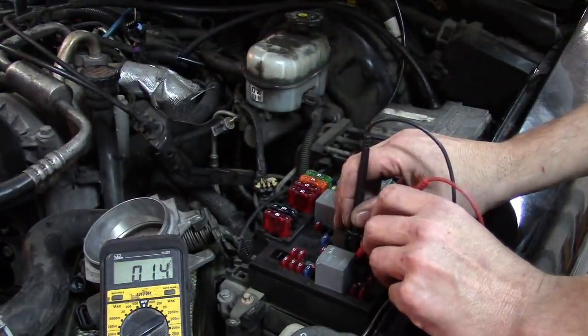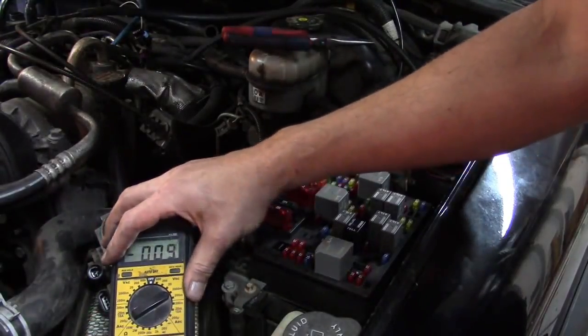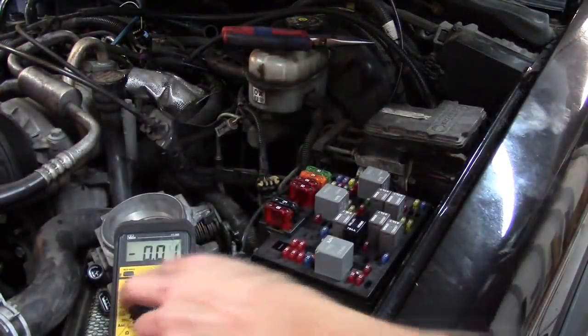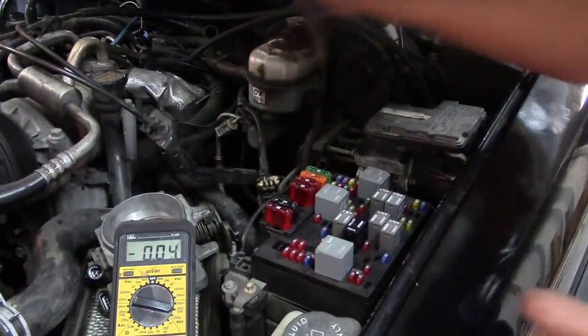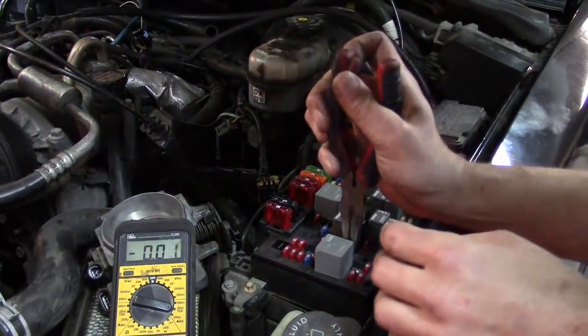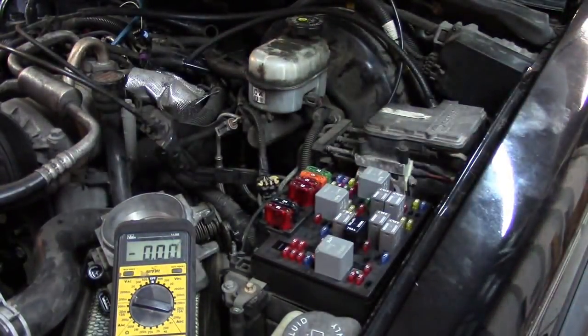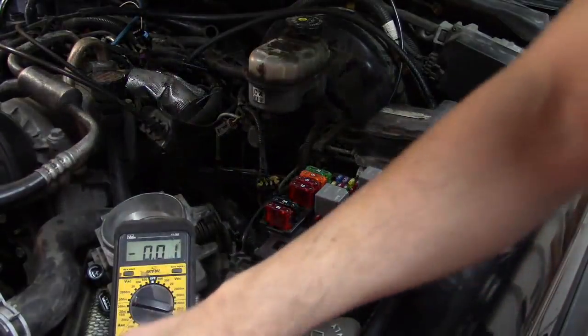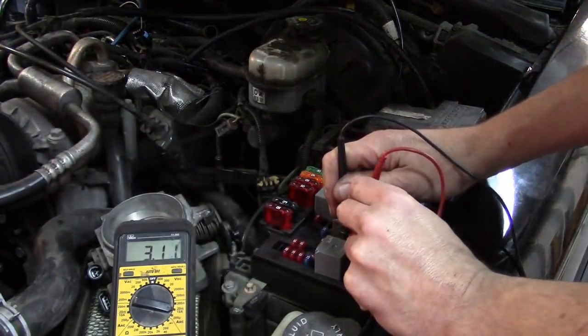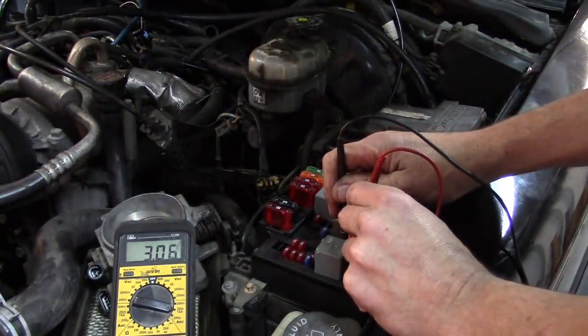Then we can reconfigure our DVOM to the 10 amp mode, and go ahead and just pull that fuse to do an actual direct amperage test on that circuit. We can see that this is drawing 3 amps on that circuit.